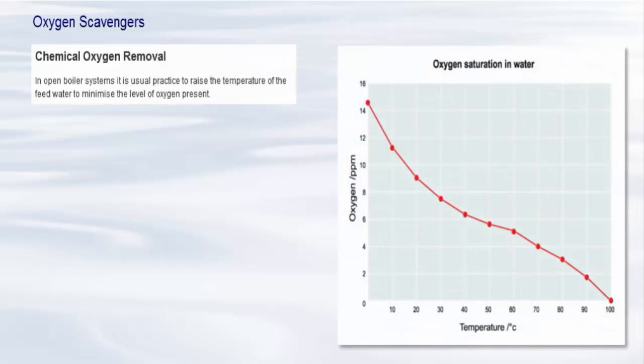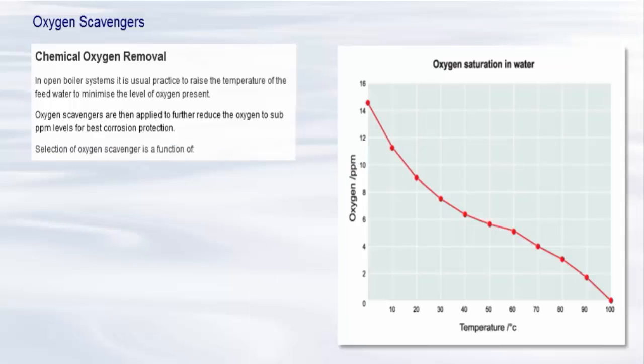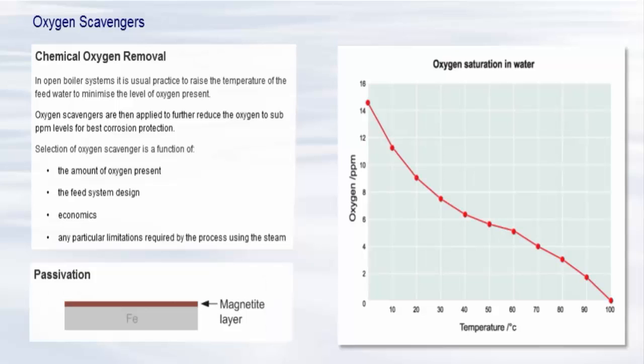In open boiler systems, it is usual practice to raise the temperature of the feed water to minimize the level of oxygen present. Oxygen scavengers are then applied to further reduce the oxygen to sub-PPM levels for best corrosion protection. There are various types of oxygen scavenger available to carry out this task, and selection of the best approach is a function of the amount of oxygen present, feed system design, economics, and any particular limitations required by the process using the steam. Some oxygen scavengers such as DEHA, hydrazine and carbohydrazide promote a protective iron oxide film called magnetite that further enhances corrosion protection.